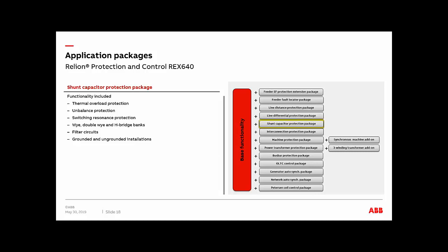We got the switching resonance protection, and it's pretty much used for detecting three-phase resonance caused by capacitor switching or topology changes in the network. So the relay has the capability of detecting when resonance is present, and it can switch off different capacitor banks. And of course, you have to coordinate it with the power factor controllers and so forth, but you can always have this scheme constructed. As long as you have the logic in place, you can have a pretty good coverage of your capacitor banks.